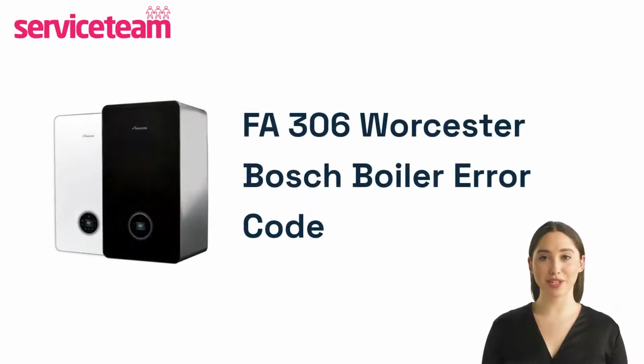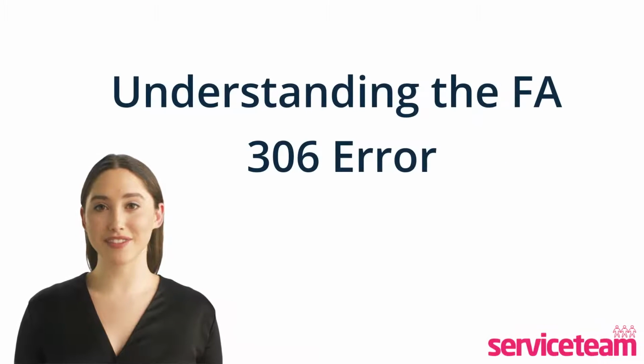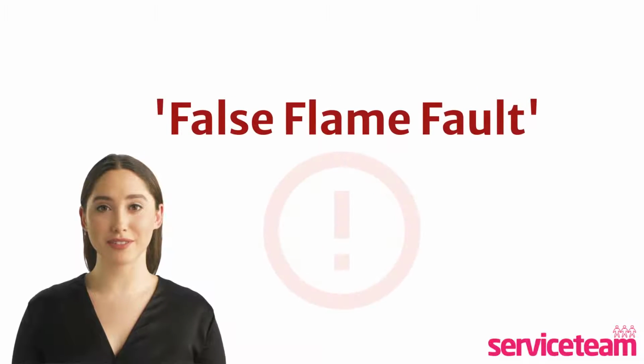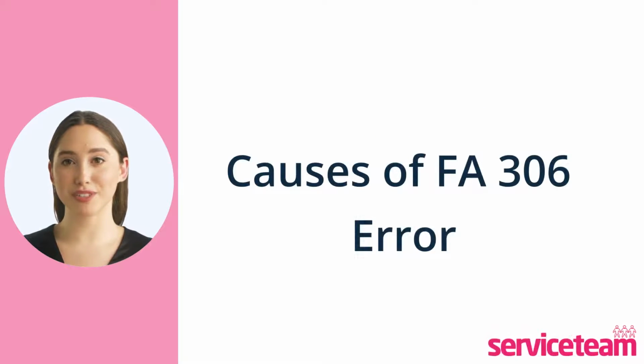Let's find out how to troubleshoot the FA306 error code in the Worcester Bosch boiler. The FA306 error often displays when your boiler senses a flame that isn't really there. We call it the false flame fault. What causes the FA306 error?